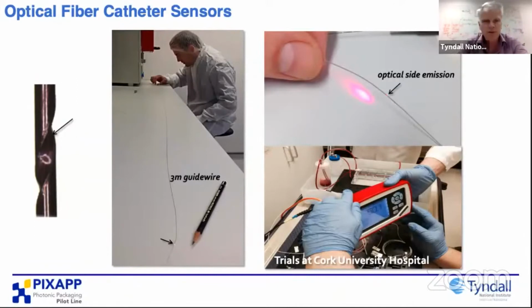And what we have here is these very narrow core fibers. These are bend insensitive fibers, pretty much bend insensitive, because as you're bending these through the vascular system, you don't want light to leak out across a bend. These would be about 50 micron diameter. Again, this region here is about, say, 300, 340 micron diameter guide wire. And the core where the light is guided is about 3 microns. So these are high numerical aperture fibers.